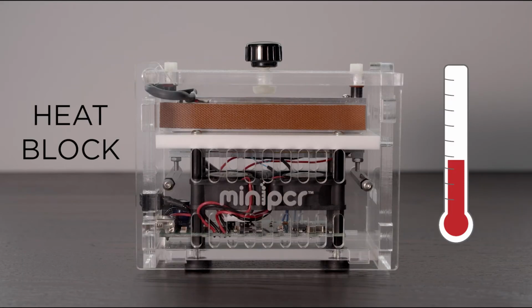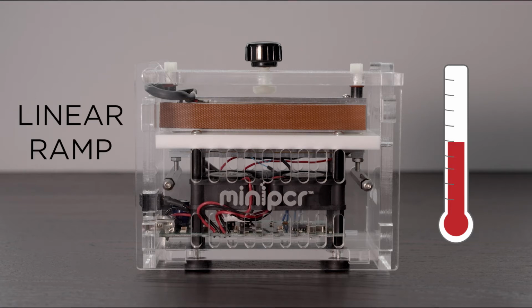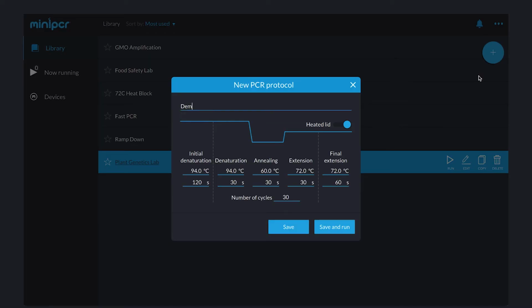The heat block option programs the machine to hold one temperature for a set period of time, while linear ramp programs the machine to start at one temperature and slowly ramp to a different temperature over a set period of time. To program a PCR, enter a name for your new protocol.